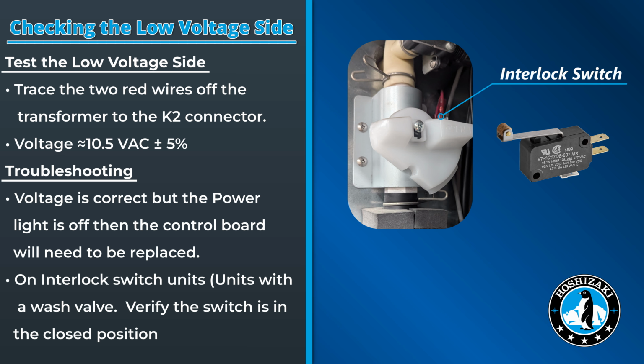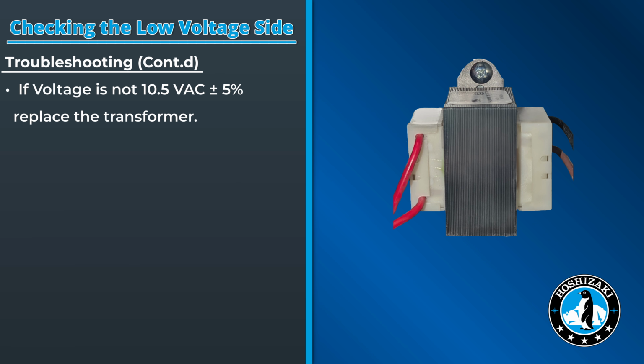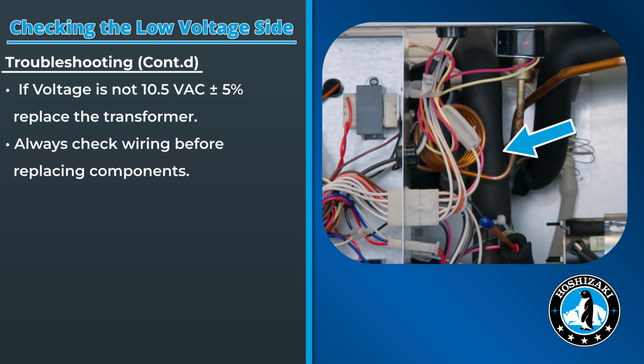If there is no voltage present and the unit is equipped with an interlock switch, verify that the interlock switch is in the closed position. If the output voltage is incorrect, the transformer will need to be replaced. As always, before switching out any components, please verify that the machine is wired properly.